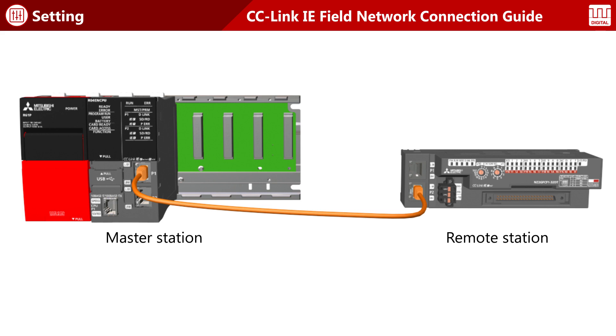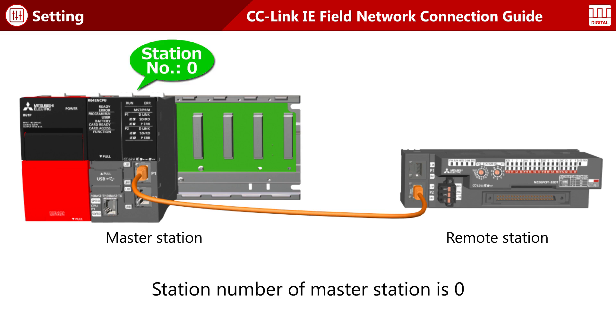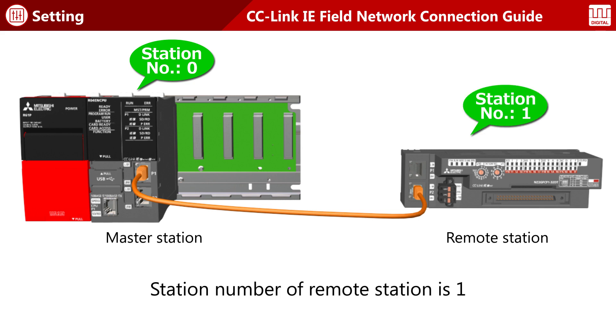The system shown here is configured with two stations. The station number of the master station is always fixed to zero. For the remote station, set the station number to one. Input and output signals are assigned between the master and remote stations.